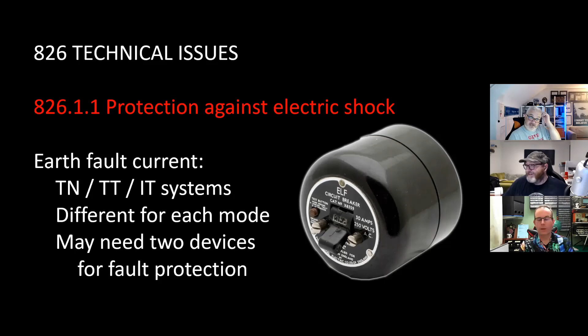So this is still on protecting against shock. Isolation of the installation is obviously something we do now, nothing unusual there, but each source must be isolated - so this is each source of energy. You also need to consider isolation from the public network. And then, as you've got multiple sources of generation, this raises the question of where is the origin of the installation, and can the origin change depending on what mode you're operating in?